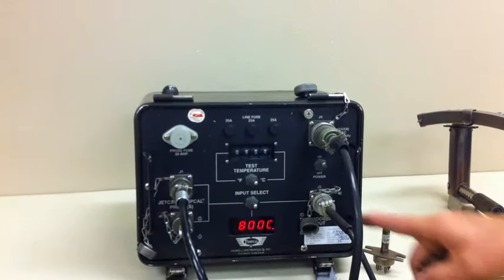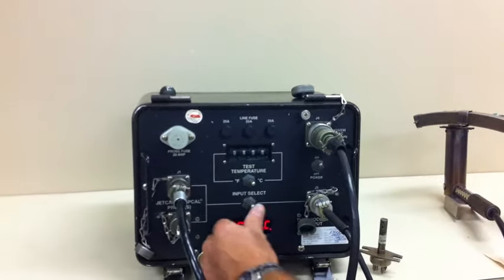So 800 degrees in, exactly 800 degrees out. That thermocouple right now is considered perfect.